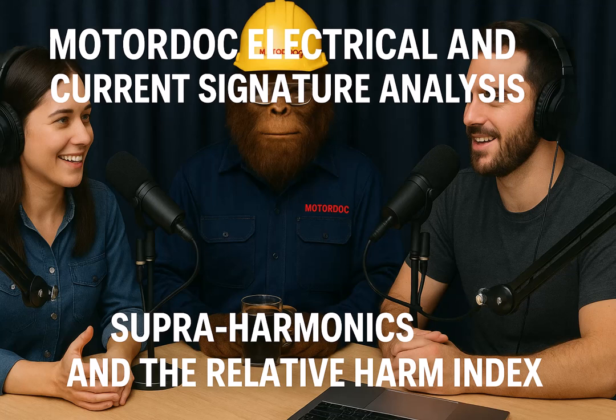The papers also mentioned sidebands at ±15 hertz, around the line frequency. What's the significance there? Ah, yes, the ±15 hertz. Those can be early warning signs of insulation deterioration, especially, again, in systems powered by VFDs, by inverters. So specific to VFDs often. They seem particularly relevant there, yes. When you see those sidebands, along with signatures for winding stress and maybe stator issues, it's a strong hint the insulation is degrading. It seems small, 15 hertz, but it can be an important early flag.